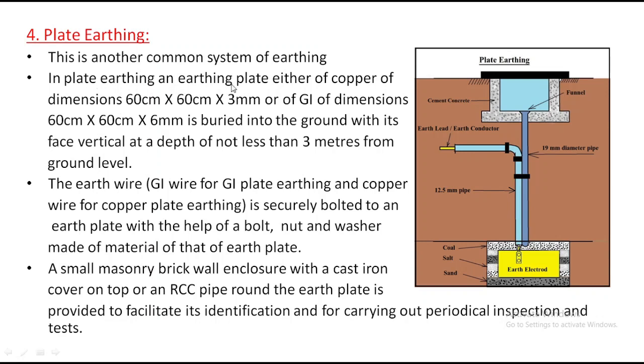In plate earthing, the earthing plate is either copper or GI. If it is copper, the dimensions are 60 centimeters by 60 centimeters by 3 mm. This is the size of the copper plate, and the GI dimensions are 60 centimeters by 60 centimeters by 6 mm. It is buried into the ground with its face vertical, at a depth not less than 3 meters from the ground level. So from this point to this point is 3 meters.